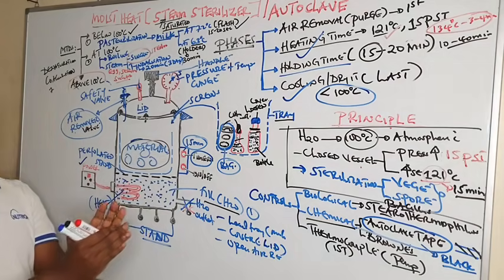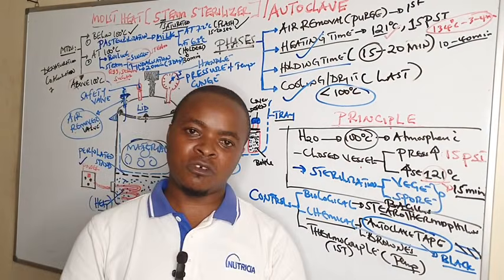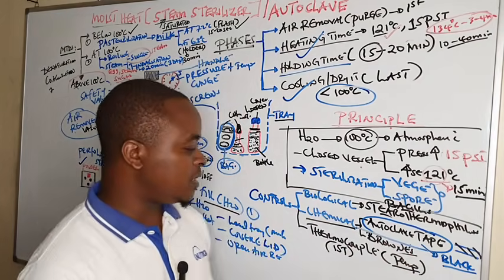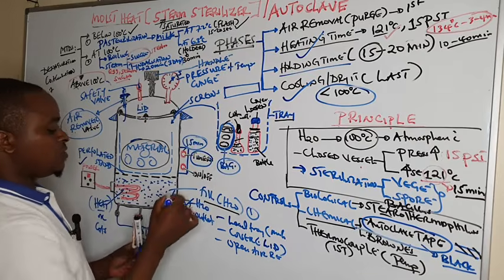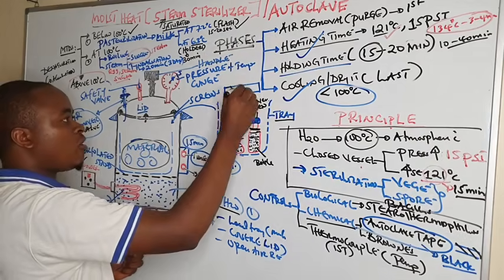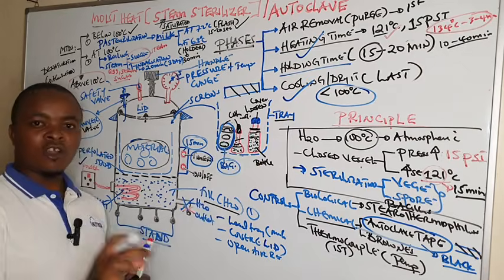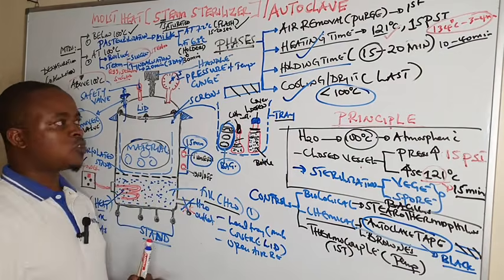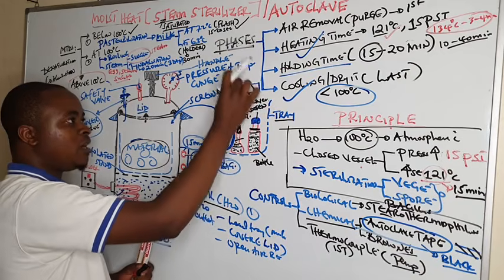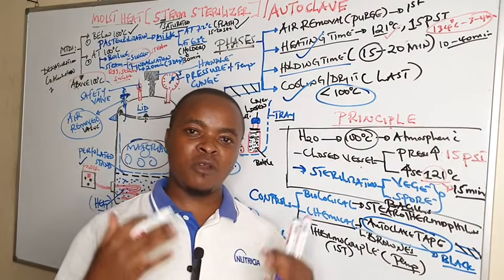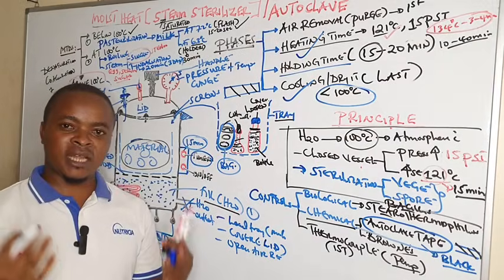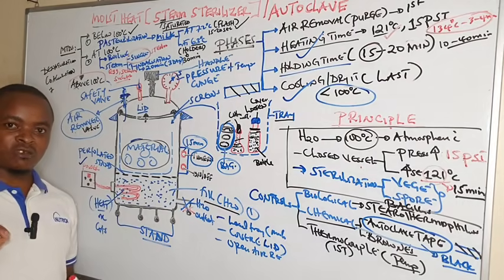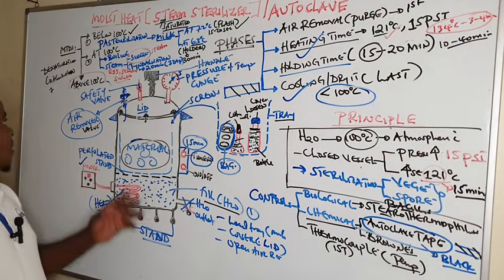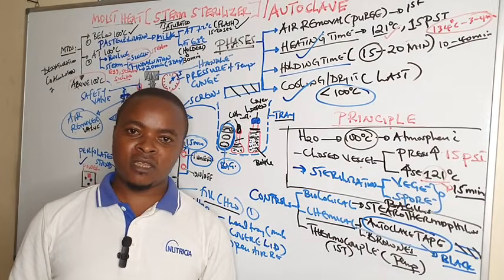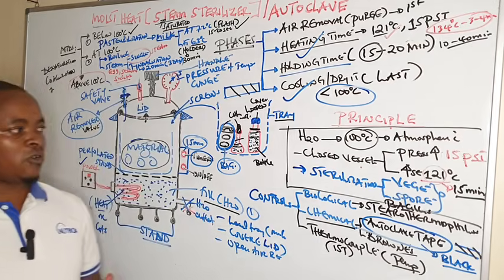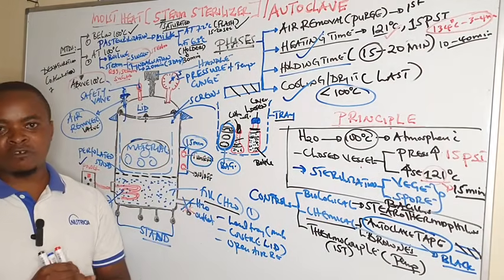And after removing the sterilized materials, the first thing you do is to check the control of the autoclave tape. What are we checking? We are seeing if the autoclave tape on the materials has developed black diagonal lines on each material being autoclaved. Because remember, you attach the tape on each material in the tray. So you check for complete sterilization by looking for the black diagonal lines in the control tape. And when you find them there, it means all materials have been sterilized by moist heat, or what we are calling saturated steam, which we said sterilizes by coagulation and denaturing enzymes and structural proteins, hence killing all the microorganisms so that we can have sterile equipment to be used in the hospital.